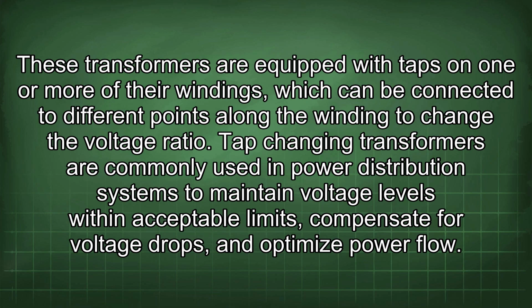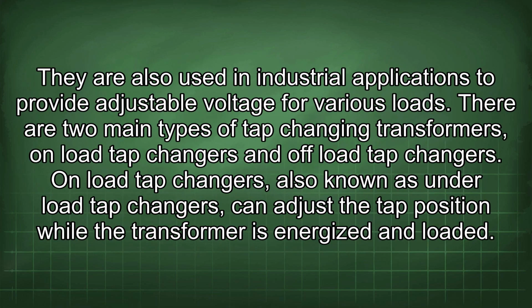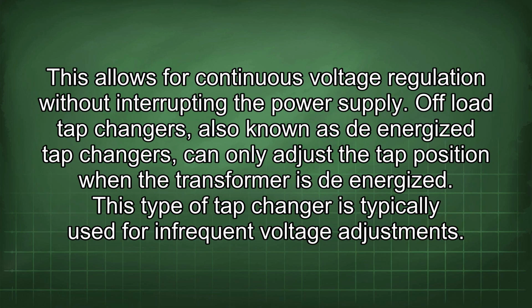Tap-changing transformers are commonly used in power distribution systems to maintain voltage levels within acceptable limits, compensate for voltage drops, and optimize power flow. They are also used in industrial applications to provide adjustable voltage for various loads. There are two main types of tap-changing transformers: on-load tap changers and off-load tap changers. On-load tap changers, also known as under-load tap changers, can adjust the tap position while the transformer is energized and loaded. This allows for continuous voltage regulation without interrupting the power supply.